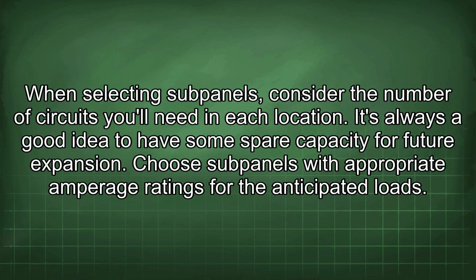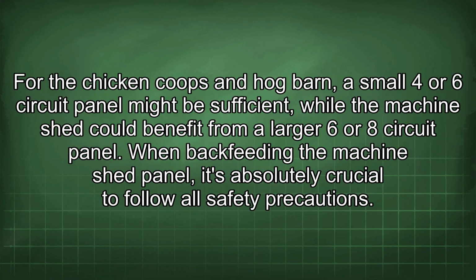When selecting subpanels, consider the number of circuits you'll need in each location. It's always a good idea to have some spare capacity for future expansion. Choose subpanels with appropriate amperage ratings for the anticipated loads. For the chicken coops and hog barn, a small 4 or 6 circuit panel might be sufficient, while the machine shed could benefit from a larger 6 or 8 circuit panel.